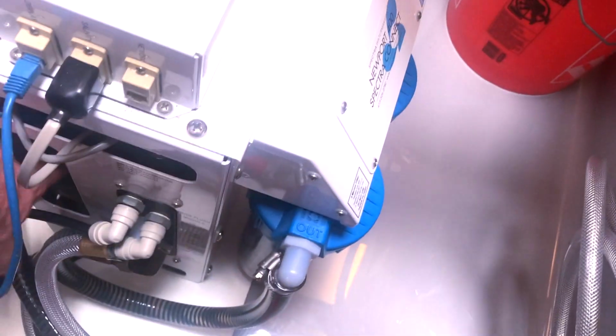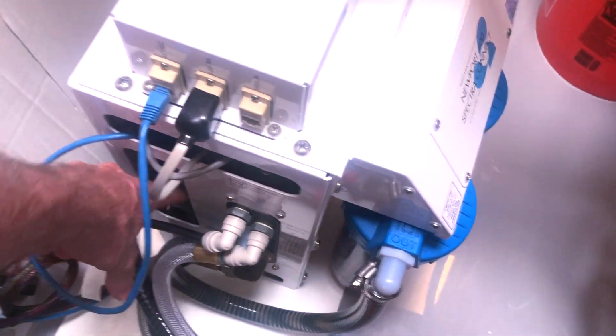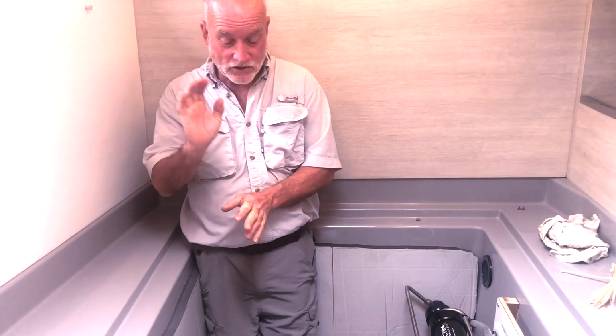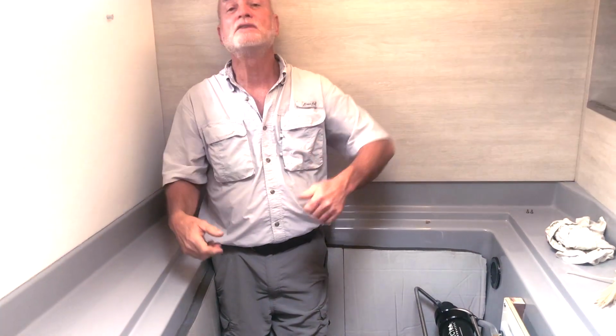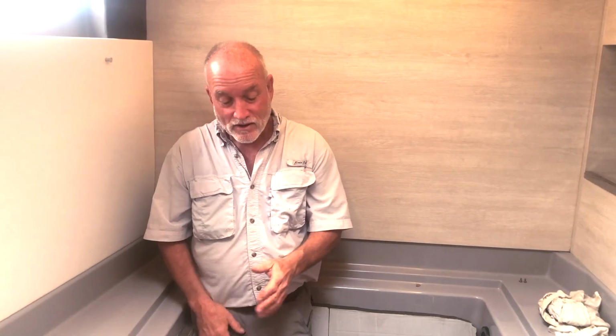What happens when the system's operating mechanically, or electronically? If you see this little button down there with my thumb on, can you see that little gray button? Yeah. Put your finger on that and see if you can feel it springy, pushing it up and down. Oh, yeah. Okay, that's the diversion valve for your fresh water, the product water being made. When it's happy with the water, it sends 12 volts to that little coil. That coil opens up, sends the water to your tank. Of course, we have no electronics, so there's nothing opening that. So as soon as you start that up, let it run for about 5 minutes. Any water that's being made is going to go overboard to the brine discharge. Yeah. Okay, now we want it to go to our tanks because we say, well, the water's good. You push that gray button down, and you turn it clockwise just a bit, and that'll lock it down. Okay. And now that'll divert the water to your tanks.